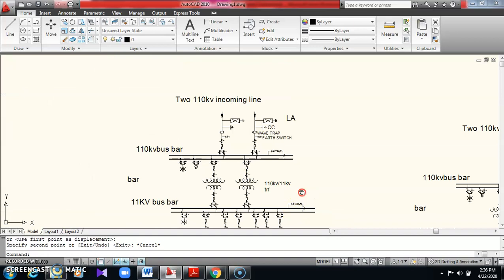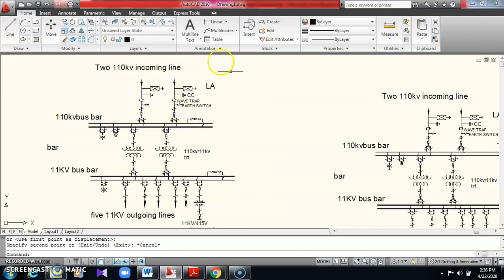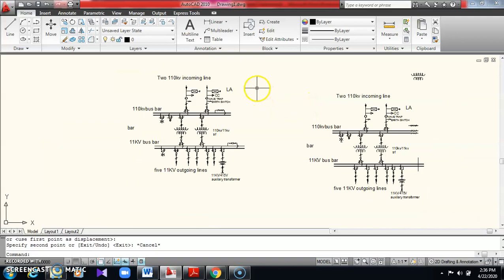Okay, getting? So this is the bus coupler. Think of the same problem if they ask for 110 kV and 11 kV sectionalized, and a total of 4 incoming lines. So 4 instead of 2 are there, but another section is sectionalized. So what you have to do here, just have a look at this diagram. You have to provide a sectionalized bus bar.